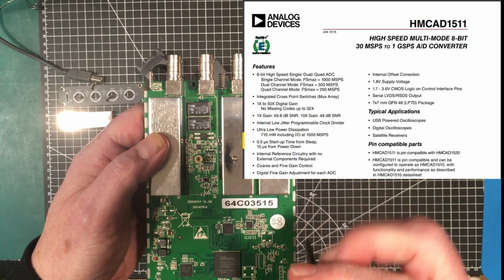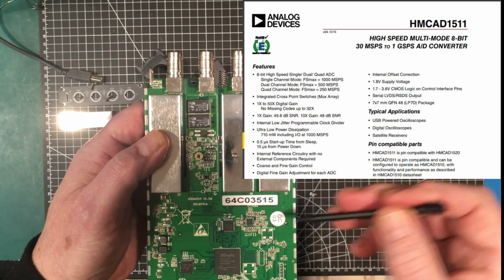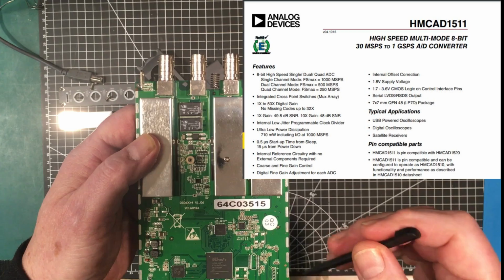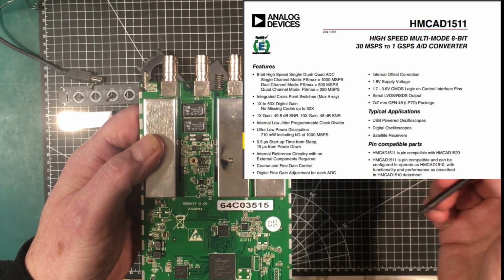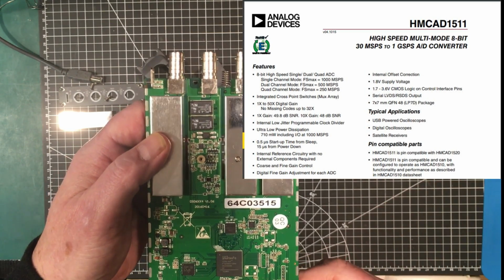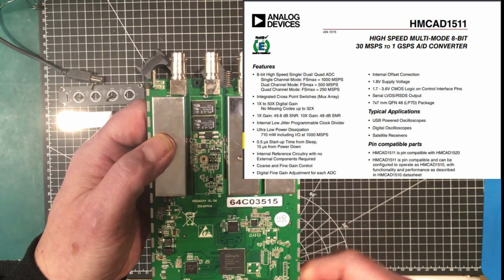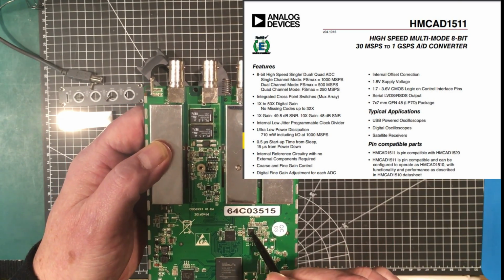So that's why at four-channel mode, you get 70 megahertz. At two channels, you get 150 megahertz. And at one channel, you're getting 260 megahertz, as we saw. And let me see if I can see what that is.